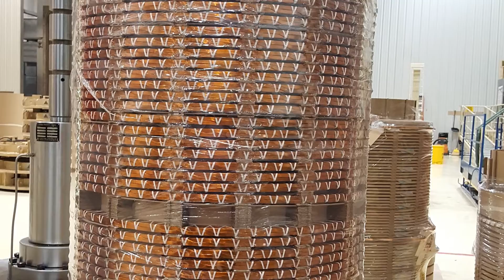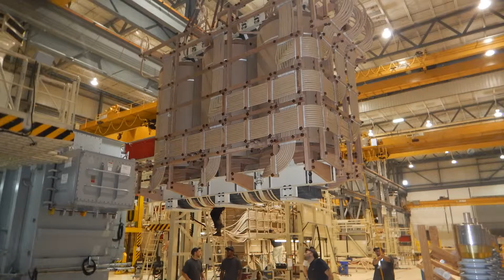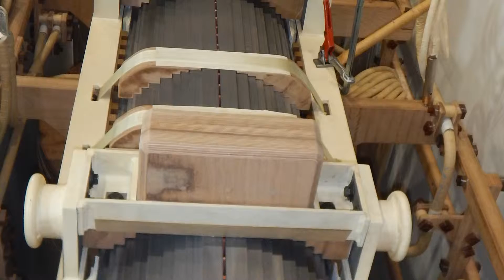There are two basic configurations of core and windings: core form and shell form. In the usual shell-type power transformer, both primary and secondary are on one leg and are surrounded by the core, whereas in a core-type power transformer, cylindrical windings cover the core legs. Shell-form LPTs typically use more electrical steel for the core and are more resilient to short circuits in the transmission systems. The shell-form transformers are frequently used in industrial applications.